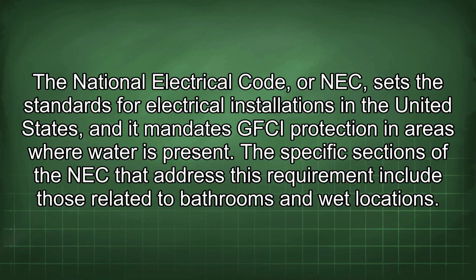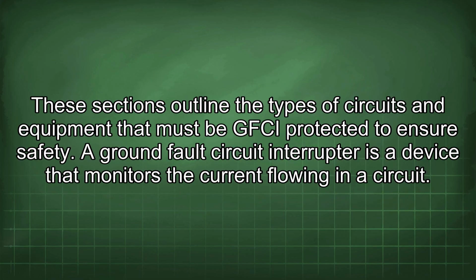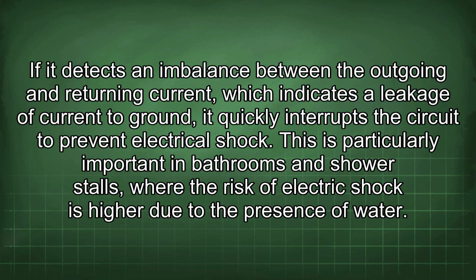The specific sections of the NEC that address this requirement include those related to bathrooms and wet locations. These sections outline the types of circuits and equipment that must be GFCI protected to ensure safety. A ground fault circuit interrupter is a device that monitors the current flowing in a circuit. If it detects an imbalance between the outgoing and returning current, which indicates a leakage of current to ground, it quickly interrupts the circuit to prevent electrical shock.